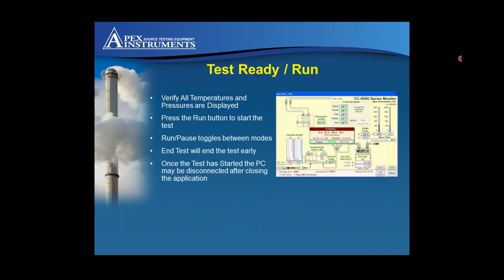This is what the actual run screen looks like when the console is running. We talked a little bit about the adjust button down in the right-hand corner. That's where I can change the time I want the test to run. I can also disable or bypass an alarm. If I have an alarm and I know what it is, it's just more of a nuisance alarm, I can turn it off until the test is over, as a temporary one-shot.